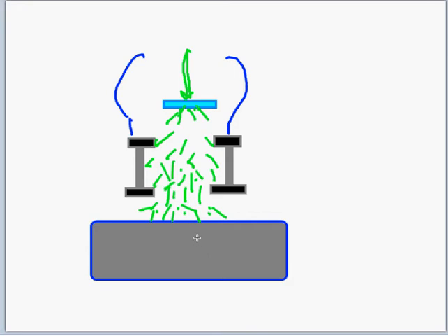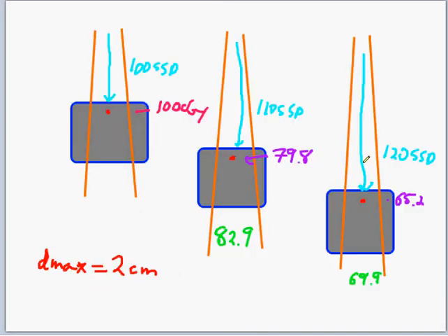So it's just because of that geometry, the fact that it's not working with electrons, that physicists came up with a factor called the virtual SSD or VSD, the virtual source distance for electrons. Let's go back here. This is how they get the idea of the virtual SSD. So they looked at what they measured. If you say you measured at 110 and 120 and you got these numbers instead of what you're expecting from inverse squared, these are the actual measurements you got.